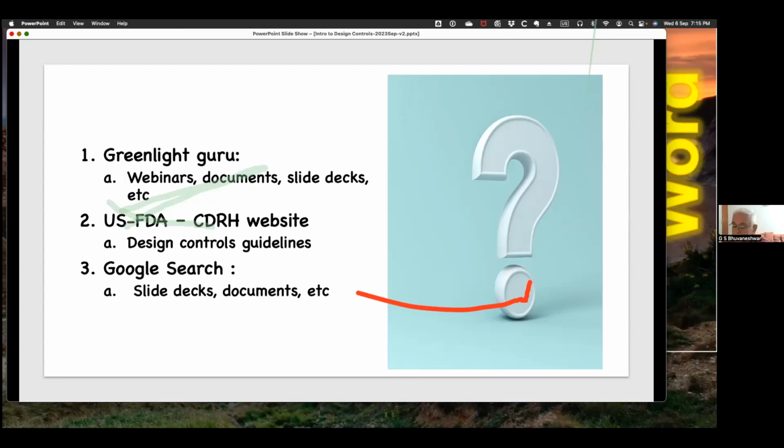Like our new heart valve, which is now undergoing clinical studies, we made a lot of design changes, including materials. So essentially, being a high-risk device, it becomes a new device. So we need to go through the full scale of all the testing and clinical studies. But a small change may not require that. So you do a risk analysis, and if you can show that the change does not create additional risks, you can go ahead and get approvals for marketing the improved product. So those are all part of design controls. Assessing risk management, going back and making sure that when you make design changes, they don't introduce new risks.